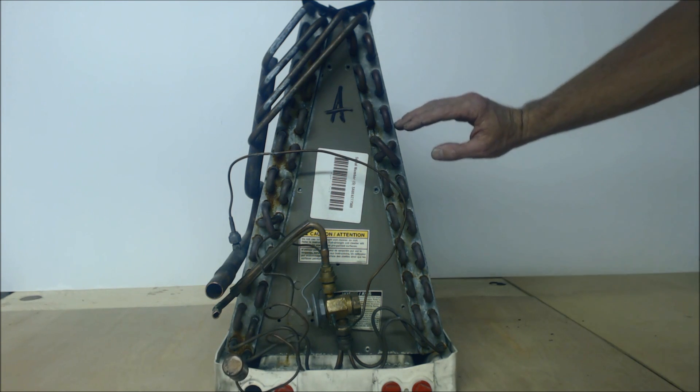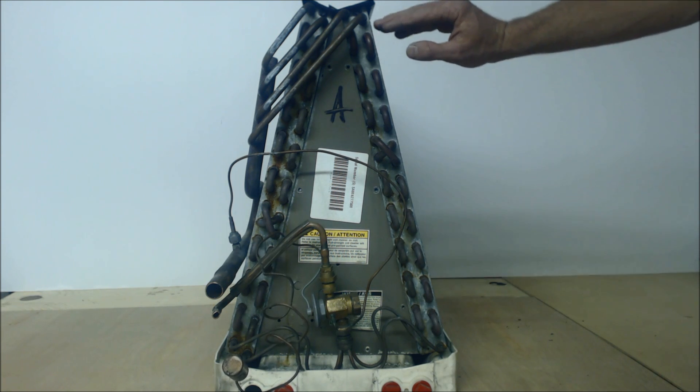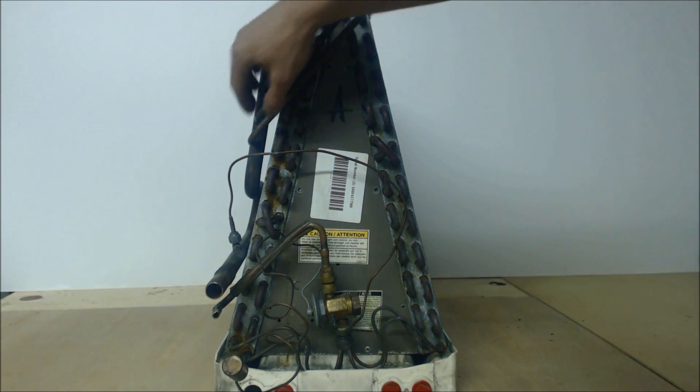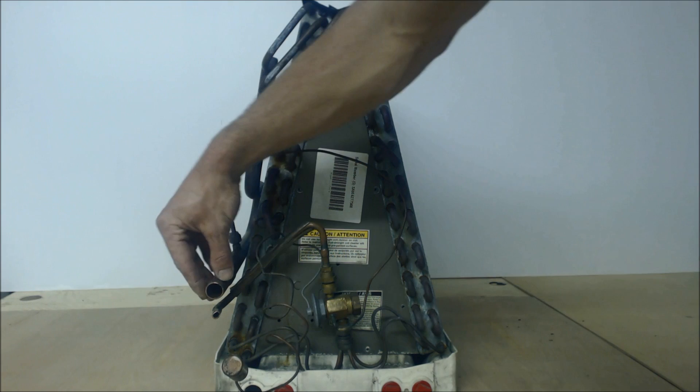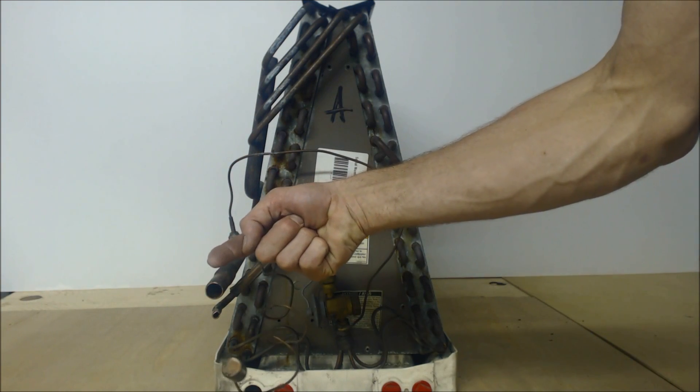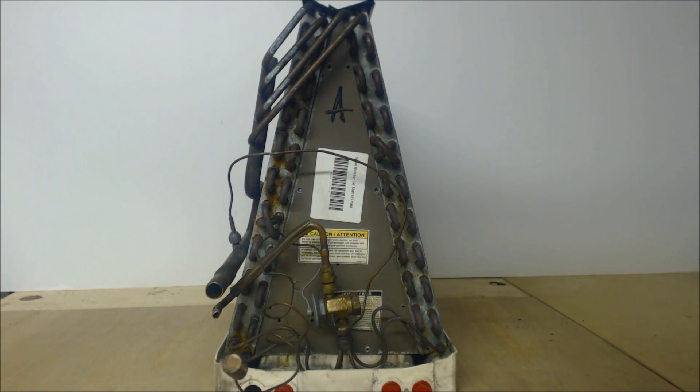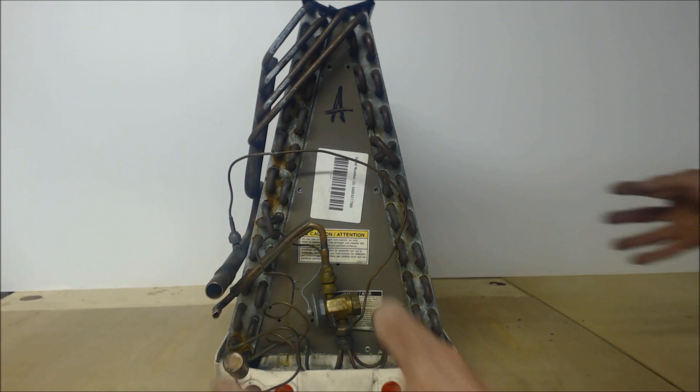From there on, it's increasing in temperature after it's turned into vapor. The vapor is getting superheated - that's the temperature increase above the saturation point. Then it comes back out through the suction line to the compressor again.